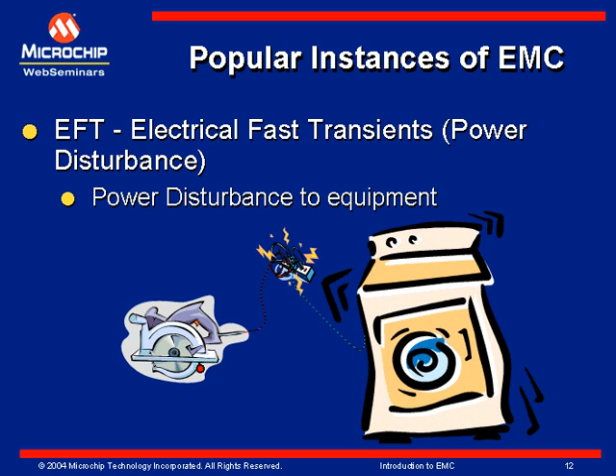As an example, anything that has an inductive load, like motors, when they are running or when they are switching inductive load, creates lots of noise on the power line. And if you have another equipment connected on the same line, like another appliance, that may be susceptible to the same noise generated by the other equipment.